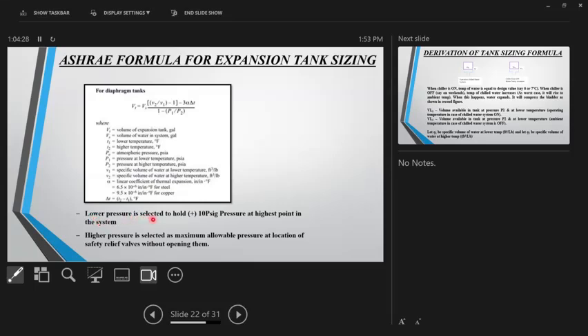Lower pressure is selected to hold 10 psig pressure at the highest point in the system. Let's say it's a tall building, a 20-30 story building. The plant room is in the basement. Then obviously the lowest pressure will be at the highest point. Now that highest point should also have 10 psig plus pressure over atmospheric. If you don't have any positive pressure, the pressure at the highest point is actually equal to atmospheric, correct? At the topmost point the pressure is usually atmospheric, but we want plus 10. So the lowest pressure in the system should be 10 psig above atmospheric pressure. So that's the lowest pressure.